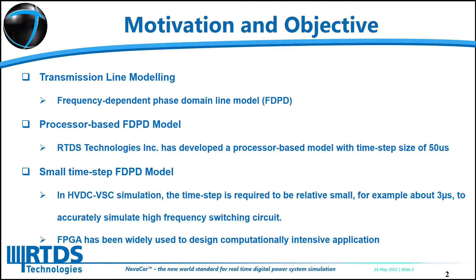I will first start off with the motivation and objective behind our work. The frequency-dependent phase-domain transmission line model performs all calculations in the phase-domain, and is considered numerically efficient and robust for both underground cables and overhead lines. RTDS Technologies has developed a processor-based large timestep model with a timestep size of around 50 microseconds. However, for HVDC real-time simulation, the timestep is required to be relatively small, for example 3 microseconds, to accurately simulate the high-frequency switching circuit.